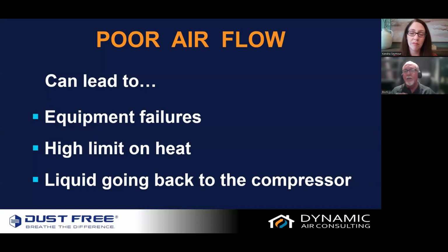Also, if we let it continue and it's operating and shutting down, operating, we're going to put a lot of stress on that heat exchanger. It's not meant to handle that great of heat, and we could compromise the heat exchanger. And then also the motors in a standard HVAC system depend on that air going across itself to keep it cool and running. Anytime we've got components that are running hot, that equals energy, and it also equals a shorter lifespan. And then in cooling, the same thing holds true for the motor, but also we could be sending liquid back to the compressor because we need that airflow for a complete refrigeration cycle.